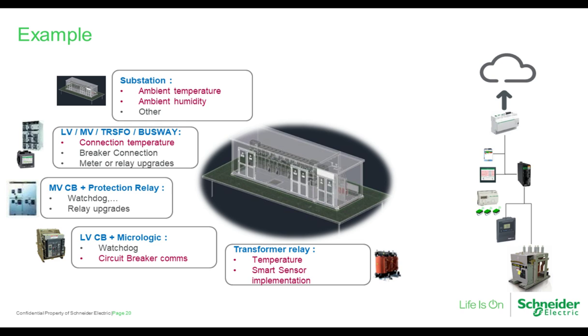We're going to add ambient humidity sensors, and then others such as partial discharge. So in a low voltage, a medium voltage, and busway, we can add these sensors throughout the equipment. Okay, and then if we upgrade the breaker, we can also look at power monitoring through a low voltage breaker, or we can add a meter or a relay.